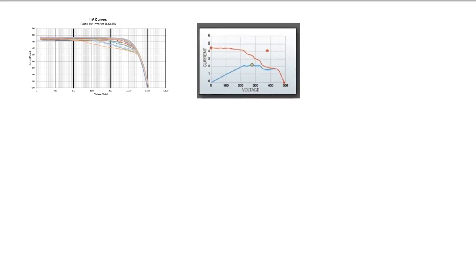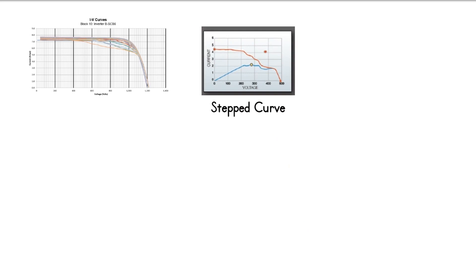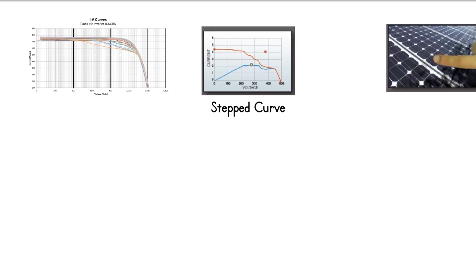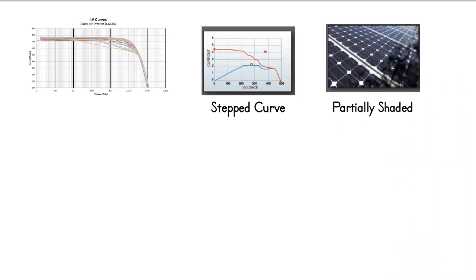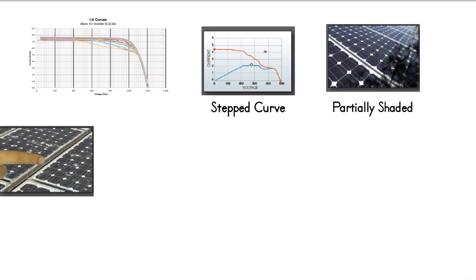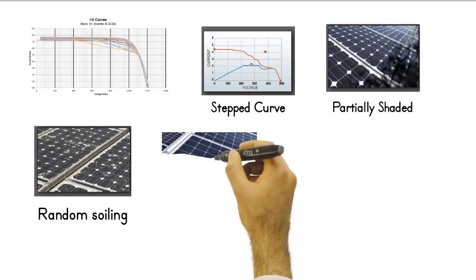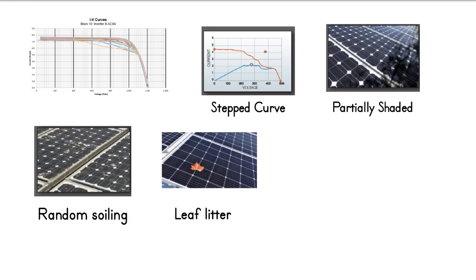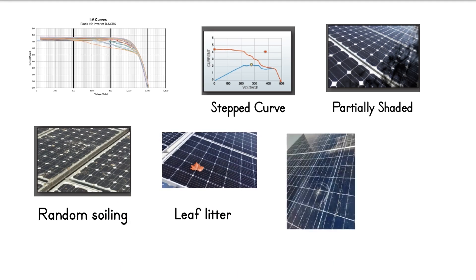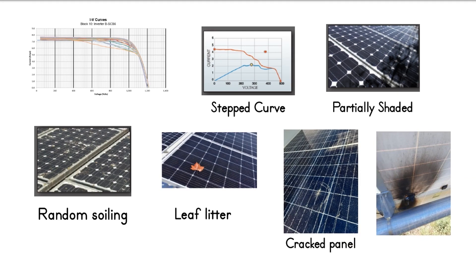The first type of deviation is the stepped IV curve. When stepped IV curve is observed, check if the panels are partially shaded. Remove obstructions or perform tests when unshaded. If there is random soiling, leaf litter or bird droppings, clear modules and retest. Also, check for cracked cells or glass, as well as burnt marks.